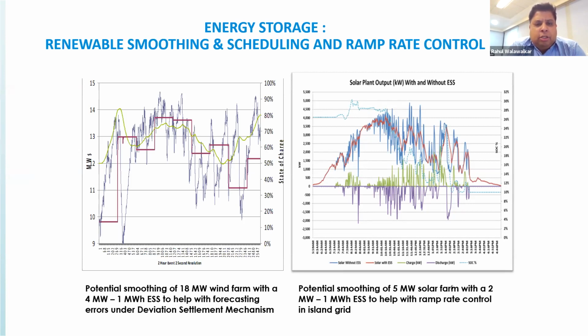The left-hand side chart shows how adding a very small amount of storage helps. In this case, we ran a simulation for a smaller wind farm with 18 megawatt wind, with 4 megawatt, 1 megawatt-hour of ESS using power batteries such as lithium titanate or lithium NMC type batteries. We showed that using this small amount of storage, you can actually stabilize the wind energy output into a 5-minute step curve, represented by the pink curve on the left-hand side.